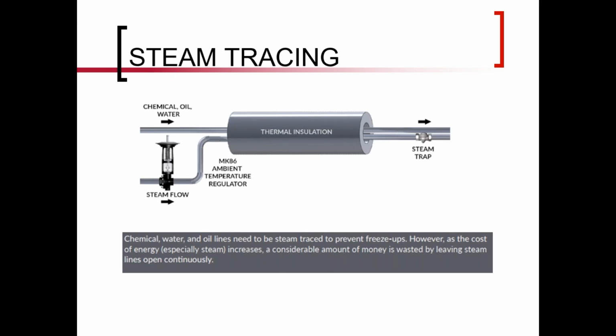So here's just a neat little diagram of how that might work, where you've got steam obviously coming in, and you've got your chemical, your oil, or we've been using water as the medium. And then once it drops down below, it lets some steam through. You've got your insulation, obviously a steam trap to get out any condensate. It's not the greatest example of how a steam trap should be piped, but we'll let that go as we're talking about temperature regulators. But here it is, taking care of that water, making sure that it doesn't freeze in your lines.